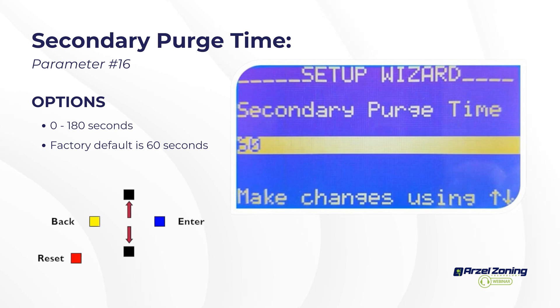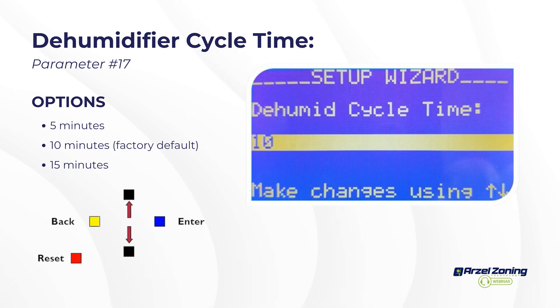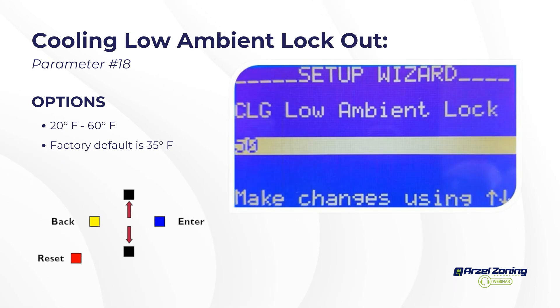Secondary purge time: the panel has two purge cycles. The primary purge holds the last calling zone's dampers open for two minutes at the end of a conditioning call. The secondary purge then de-energizes every zone solenoid and continues running the pump — typically 60 seconds — to drive all dampers fully open before shutting off. Dehumid cycle time sets how long Y1 runs on a dehumidification call: 5, 10, or 15 minutes. Longer runtime removes more humidity but increases the risk of over-cooling.